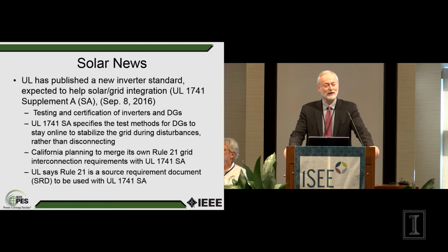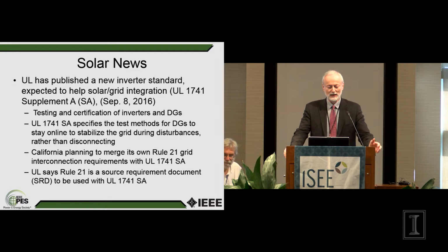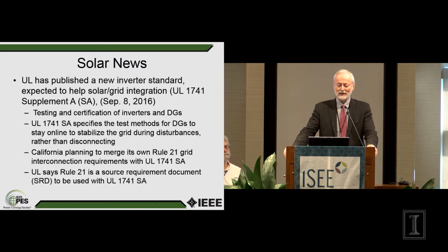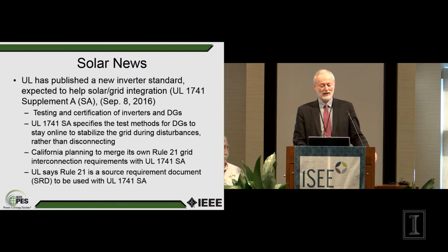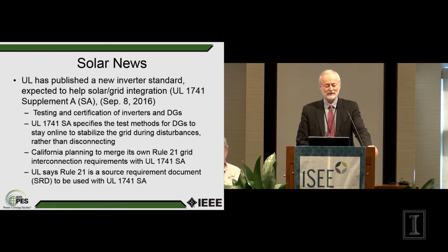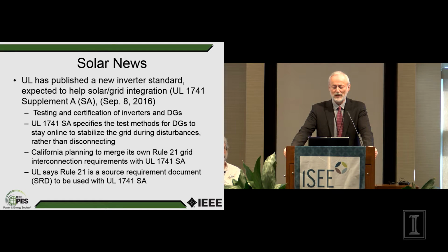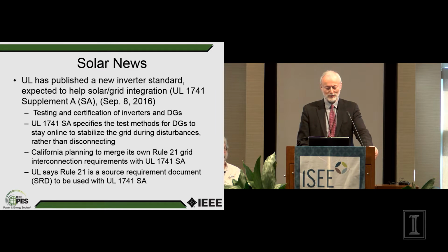One requirement is required ride-through in case of disturbances. This new inverter standard, UL 1741 Supplement A, enables testing and certification of inverters for distributed generation—test methods and the ability to stay online to stabilize the grid during disturbances. This is the first time such a standard has actually been accepted and implemented, and California is merging it with its own Rule 21 grid interconnection requirement, used as a source document for implementing solar.